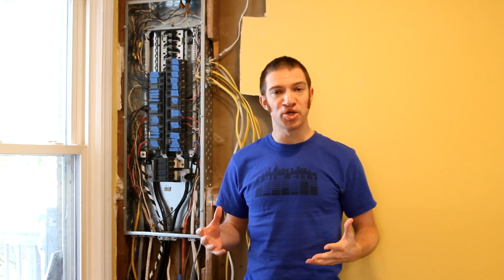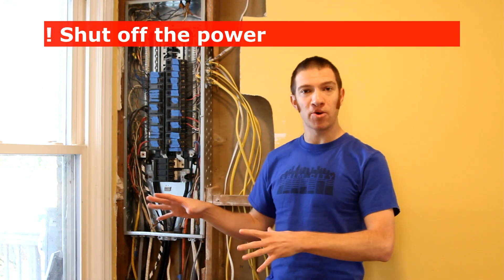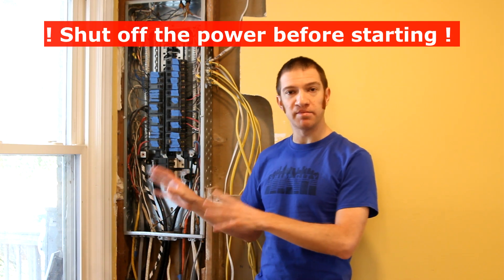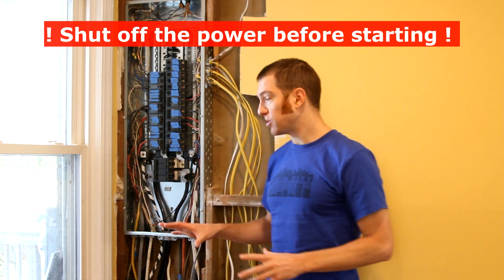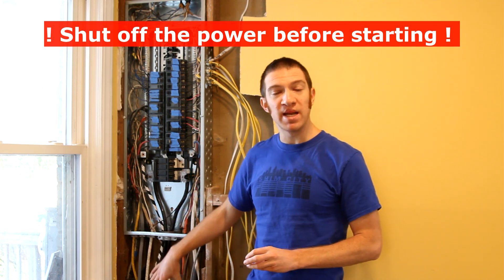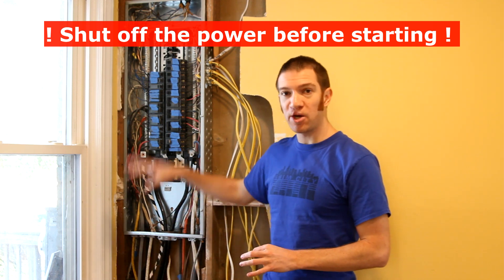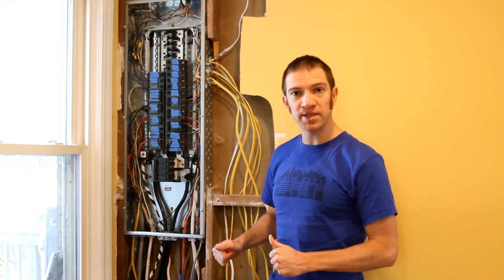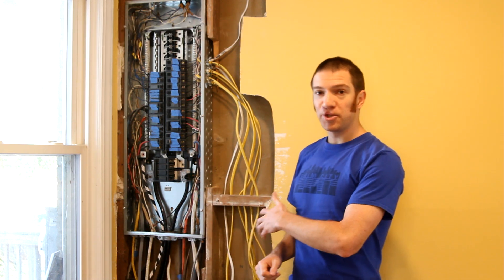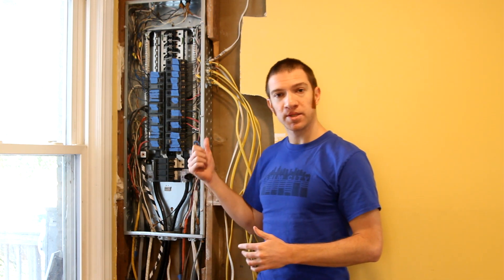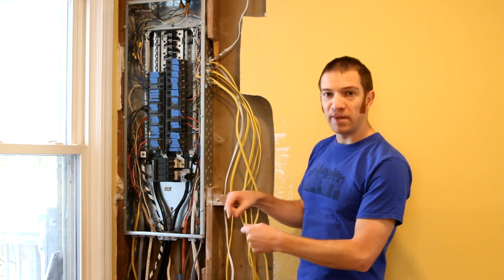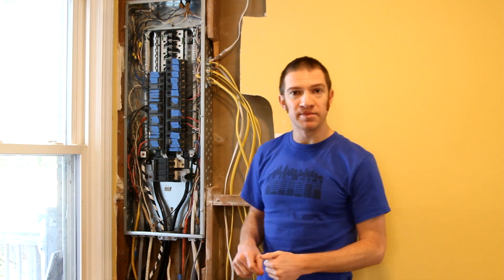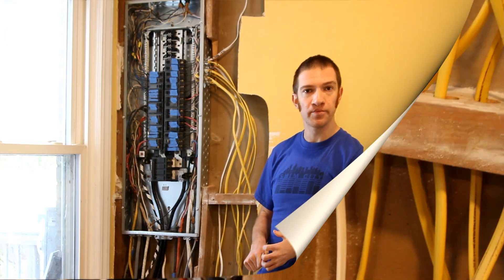So now that you've got all your permits, you've done all your prep work, it's time to go ahead and get your power shut off at the meter. And we do that just so that it de-energizes your main feeder line. Now your entire panel is without electricity, and you need to start disconnecting stuff. Disconnect all your breakers, disconnect all your clamps, and I try to pull things out and make sure that the wires themselves are labeled so that it'll be easy to reconnect everything.